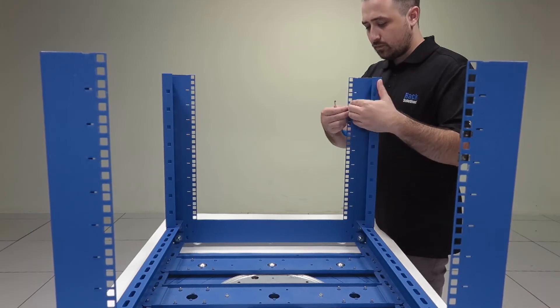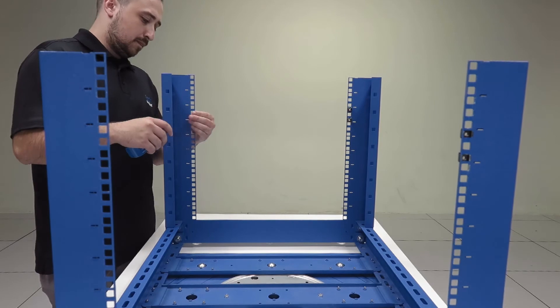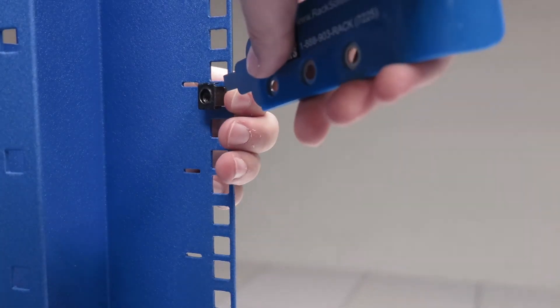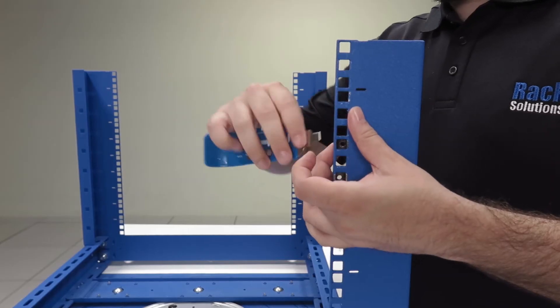If you're using a round or threaded hole rack, the process will be mostly the same except you won't use cage nuts. Insert one side of the cage nut prong into the rack, then grab your tool and push the other side in. You can do this with your hands, but it might possibly hurt.